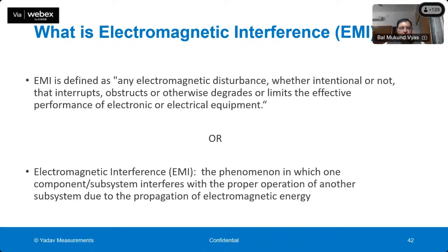Then another very important test nowadays is the electromagnetic interference test. The meter itself is an electronic device, and of course the meter is subjected to lots of electromagnetic interference. One very common example is the mobile phone, which works based on radio frequency. Radio frequency is there in the air everywhere. We have mobile towers. If the meter is very close to an airport, then there can be radar frequencies. Then there are satellites, police communications, Bluetooth, Wi-Fi. All these create electromagnetic fields in the air, which the meter also sees.